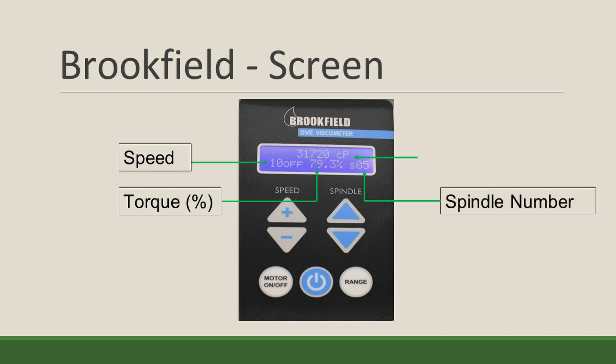On the screen you have the speed of the spindle which you can control, and the torque percent which should be between 10% and 100%, which helps determine if you have the right speed and spindle for your product. You also have the identity of the spindle you are using. On the top you have the viscosity reading in centipoise. The Brookfield is one of the most common methods to measure viscosity in quality control and quality assurance settings.